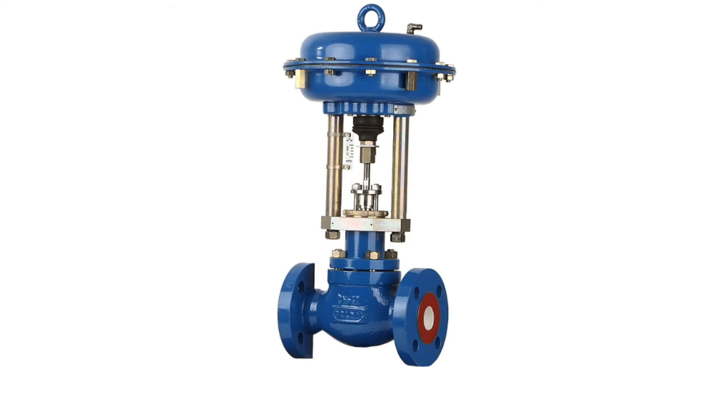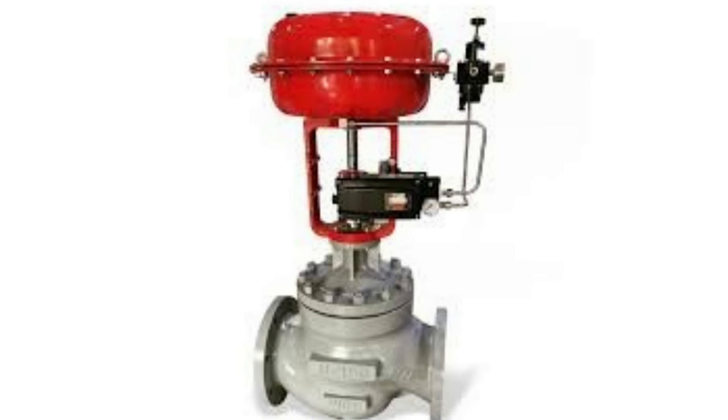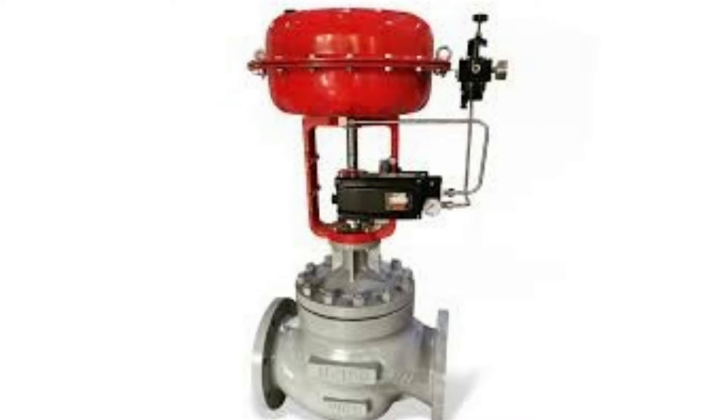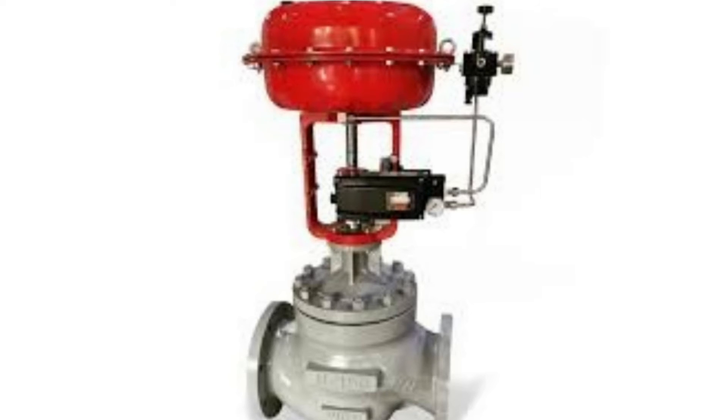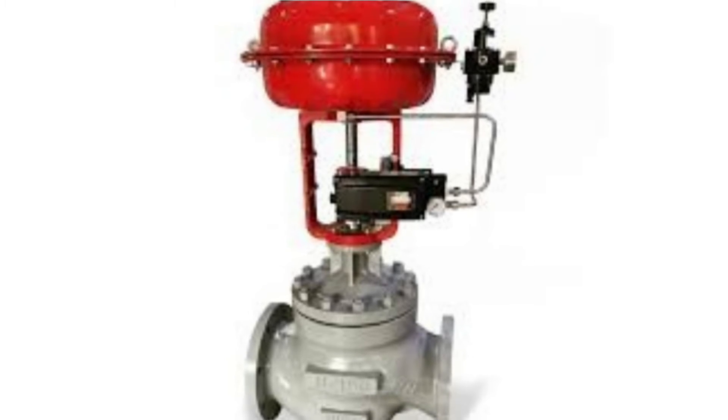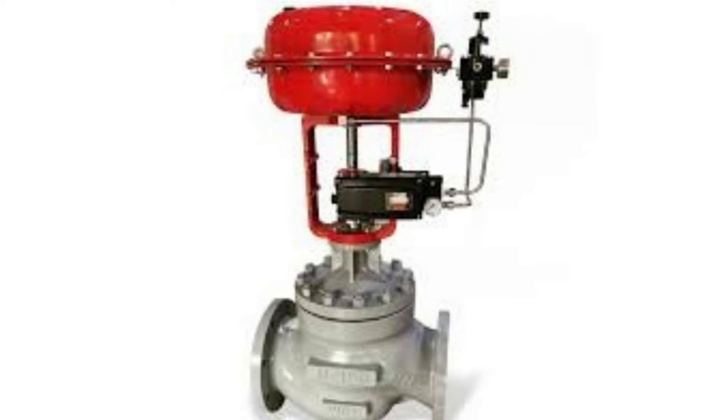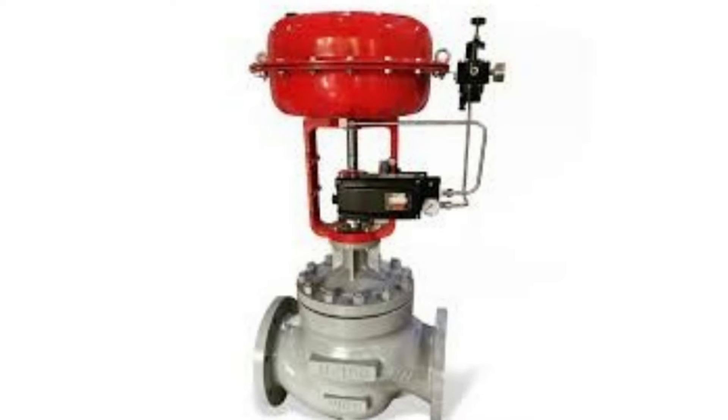The air is required and the volume of air output from pneumatic controllers won't be enough to position the valve. So the positioner will convert the low volume control air signal to a higher volume air pressure, and this is sent to the actuator to position the valve.